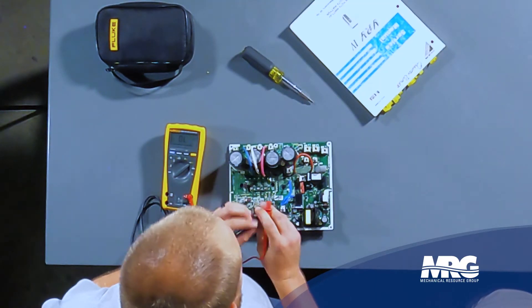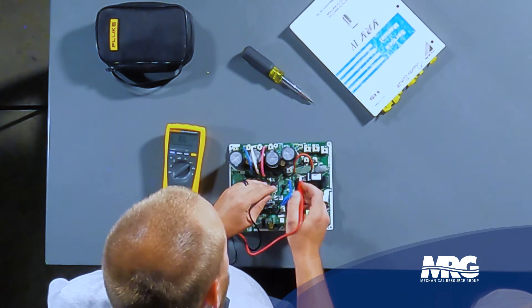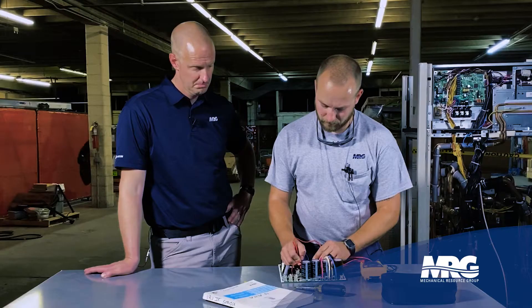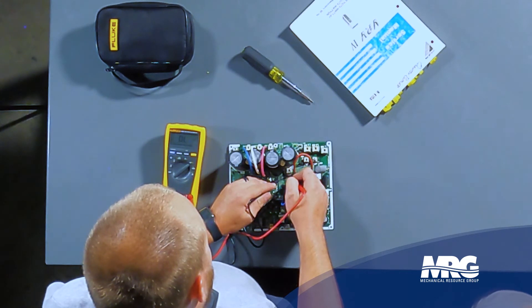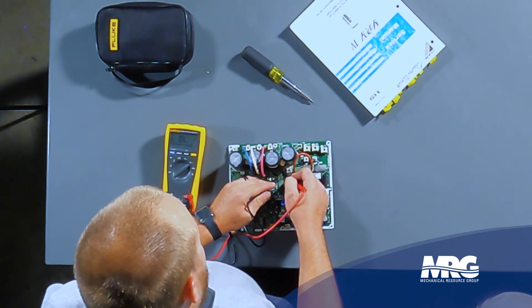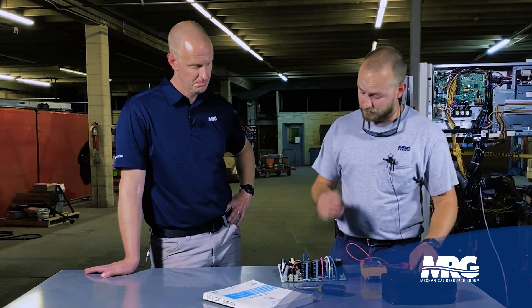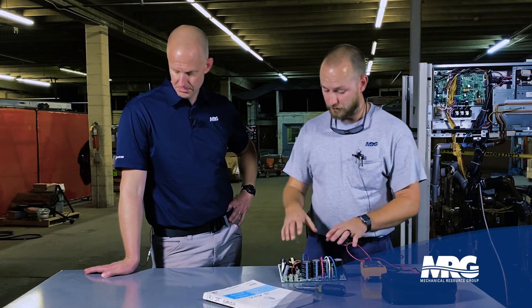So now we're going to swap our terminals around again. We're going to use our black meter lead on negative, red meter lead on terminal one, we have OL. Red meter lead on terminal two, OL. Then red meter lead on our third terminal, we have OL again. So by judging this test here, the diode bridge on this particular inverter board is in good shape. We took this out of a functional unit just for video's sake, but that's exactly what we're looking for. This is a good functional inverter board.